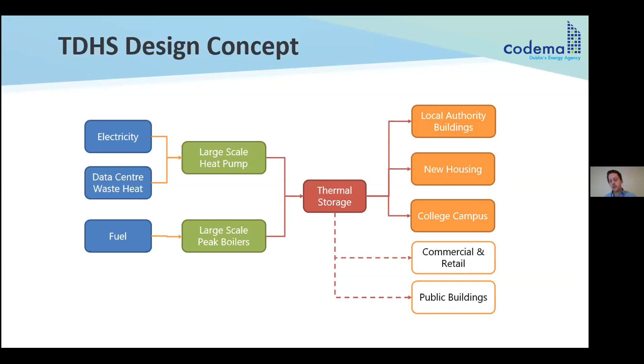The general design concept for the Tallaght scheme is: we're taking the waste heat from the data centre, passing it through large scale heat pumps to upgrade the temperature to a usable level. Then we're looking at thermal storage to balance out the peaks and troughs of demand, and also help balance the electrical grid, so it's a very cost effective method of storing energy. And then we've got our backup system, large scale peaking boilers for times when the heat pumps might need maintenance, etc.